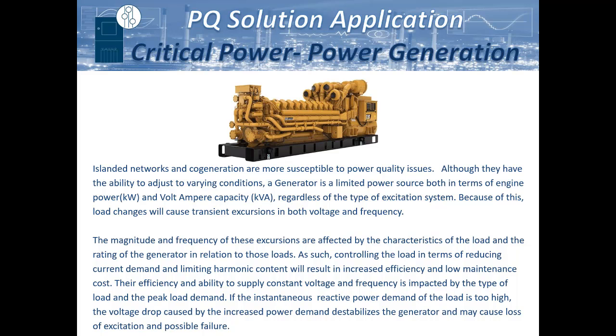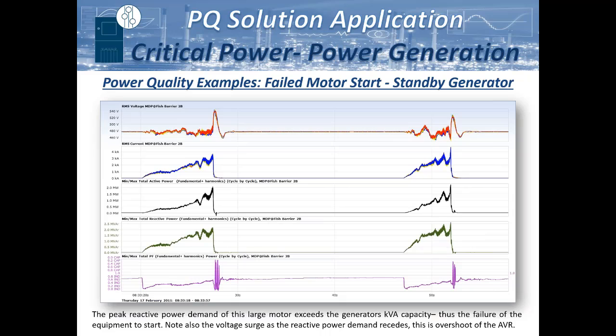So we've had long-standing experience with CAT, with Caterpillar, with Cummins, because of how our system operates, it's the only system that can effectively work on a generator network. You can see in a generator, oftentimes when an event occurs, like a motor start, they have integrated AVRs, or automatic voltage regulators. But as you can see, in this case, this is a failed motor start, because due to the lack of reactive power availability from the generator, it can impede the startup process.